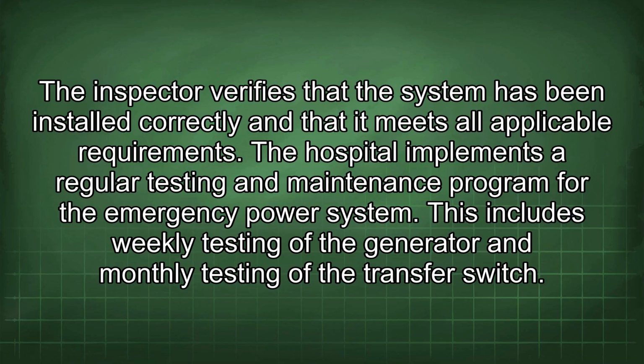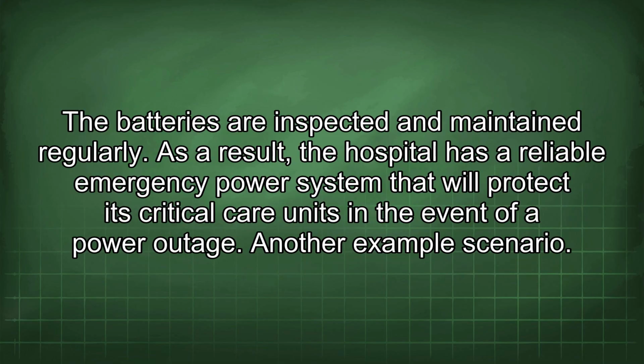The hospital implements a regular testing and maintenance program for the emergency power system. This includes weekly testing of the generator and monthly testing of the transfer switch. The batteries are inspected and maintained regularly. As a result, the hospital has a reliable emergency power system that will protect its critical care units in the event of a power outage.